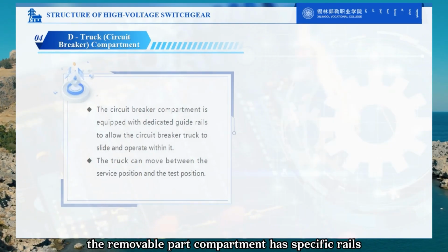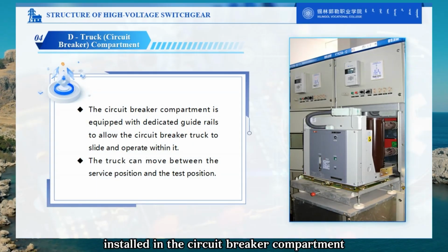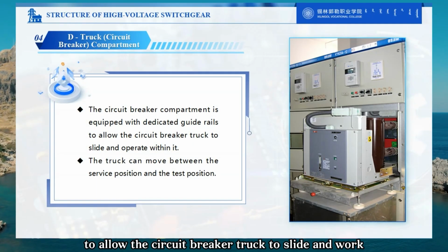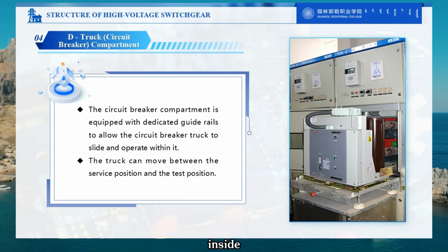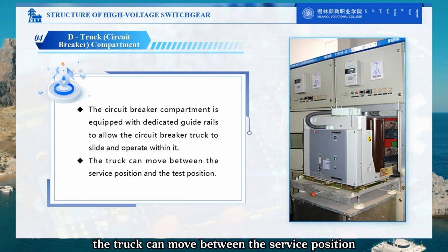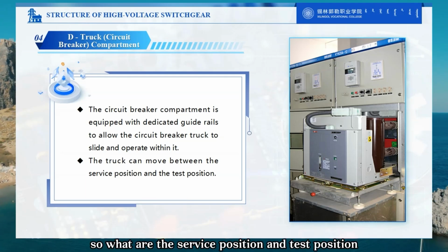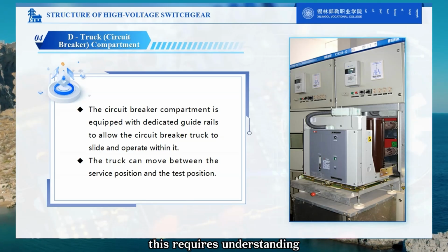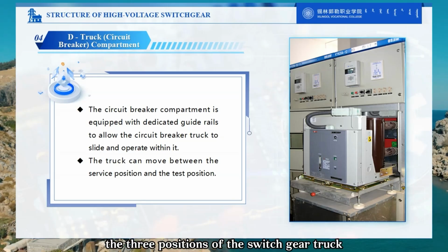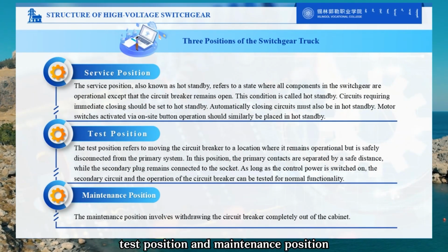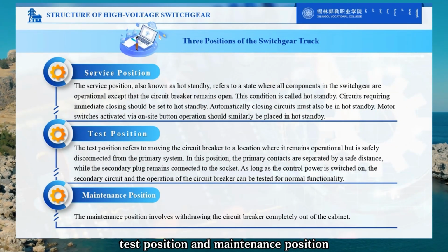The withdrawable part compartment has specific rails installed in the circuit breaker compartment to allow the circuit breaker truck to slide and work inside. The truck can move between the service position and test position. So, what are the service position and test position? This requires understanding the 3 positions of the switchgear truck. The switchgear truck includes the service position, test position, and maintenance position.